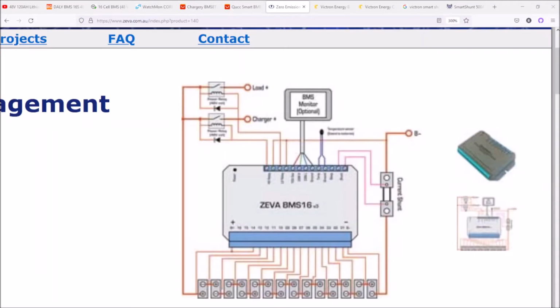My preference is a system similar to what's illustrated here. It's a little more complicated in the wiring, in that the temperature probe is separate, the shunt is separate. You have a separate contactor that's not integrated. There's control wiring for all of these devices. And still you're left with the problem that the contactor consumes a fairly large parasitic load.